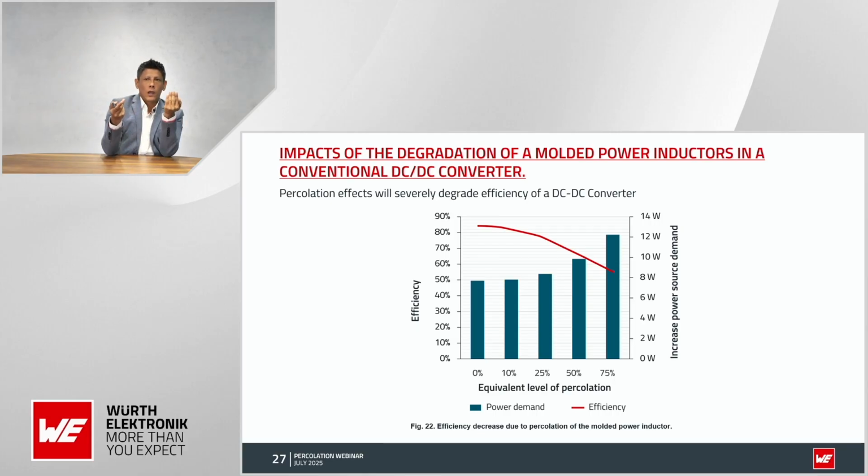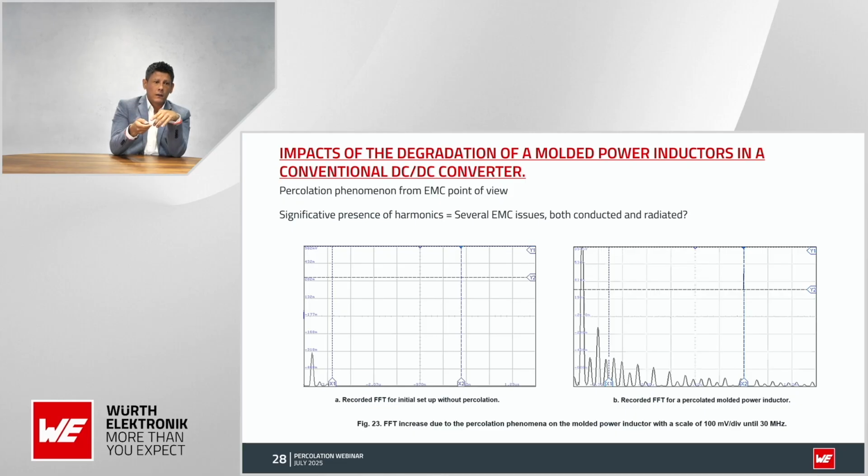You do everything, all the maintenance. But even though you are going to see a decrease in the efficiency, on the other hand, a strong increase of the power demand. And that is not speaking about just energy itself, but if we go back to the increase of the harmonics, is this an increase of the EMC? So we are going to speak about radiated or conducted EMC, because for sure that amount of energy is going to be present in the inductor, and for sure the temperature is going to increase.